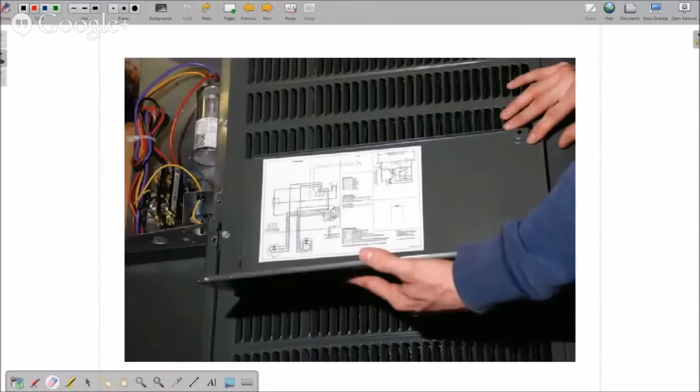Again, this is for my HVAC technician course. So if you're an HVAC technician already, you're familiar with some of this, but just to give you a quick brief, the schematic diagrams that you'll find are almost always on the inside cover of the equipment that you're working on, whether it be a rooftop system or a residential system. So if the outdoor unit, you take the cover off to the electrical panel over here, it will have some type of schematic diagram, and the same with the indoor unit. And if you're lucky, Trane sometimes has service specs, which has even more information for you. And if you're unlucky, then this will be completely destroyed, and you're going to have to rely on chasing wires to do it.